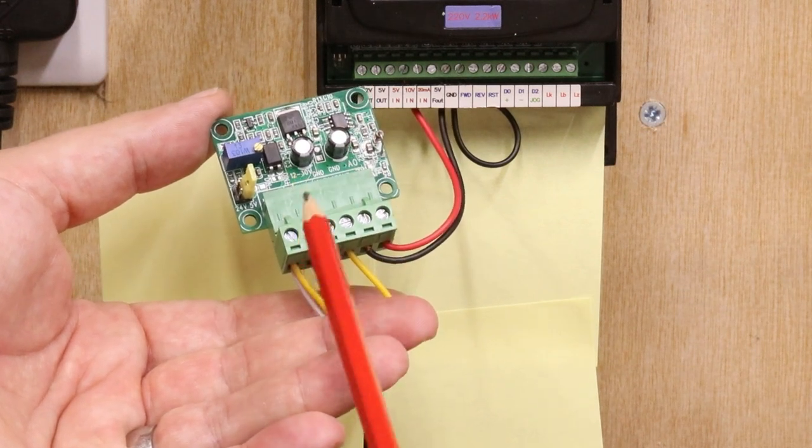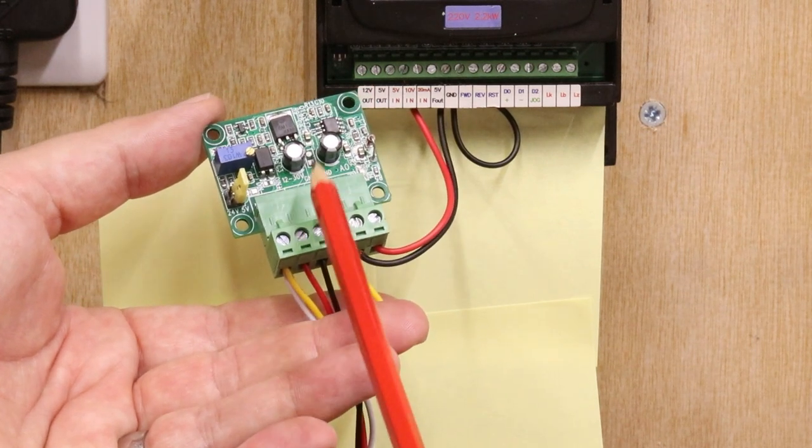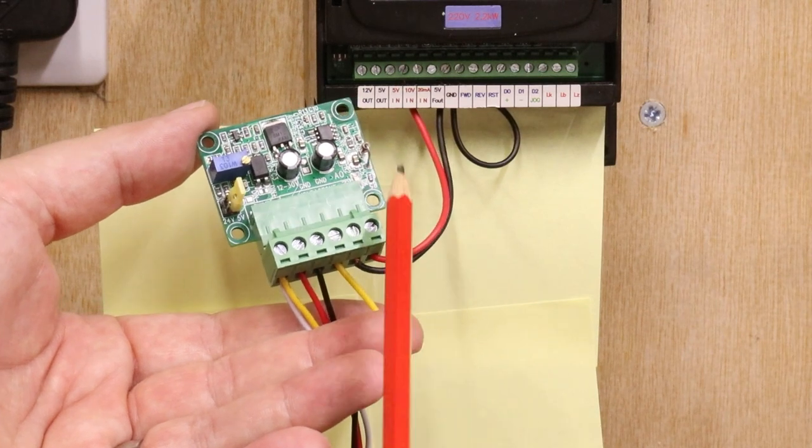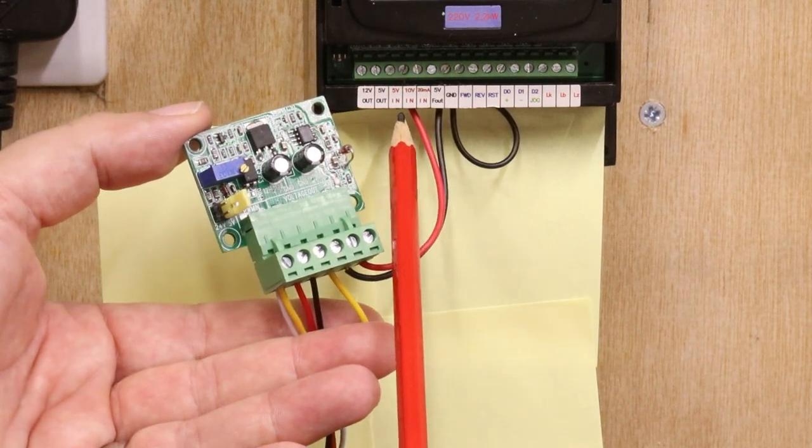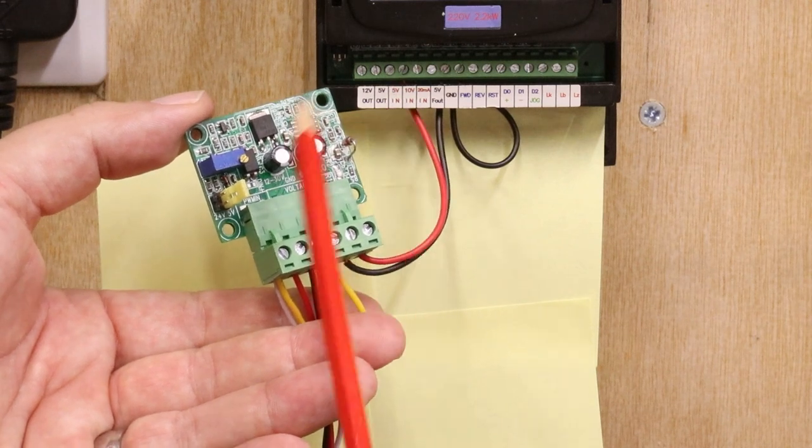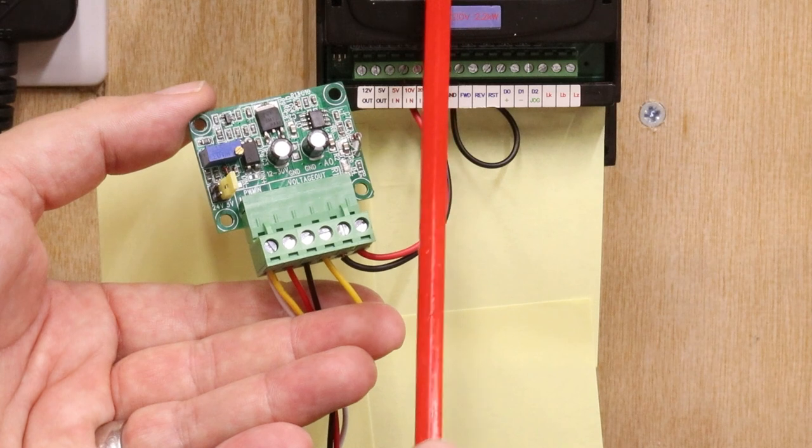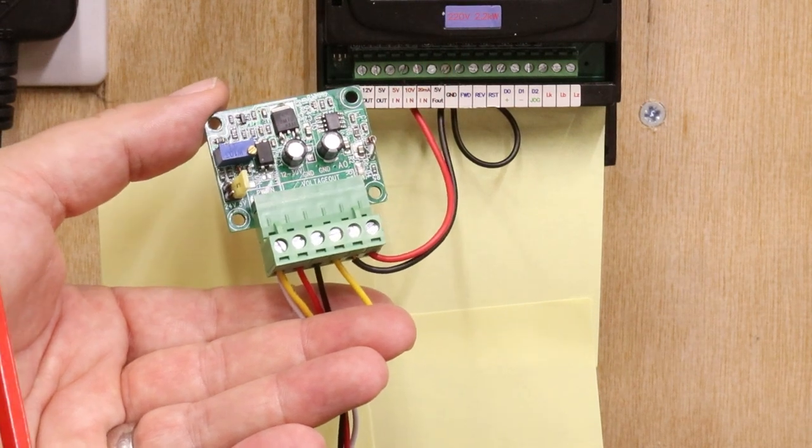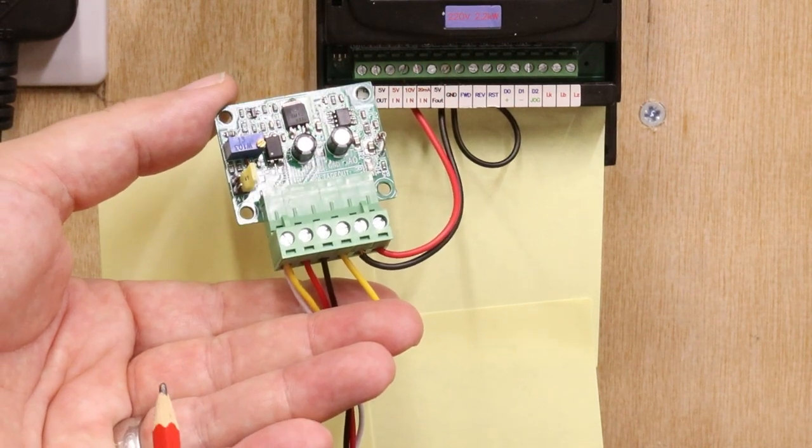Now the difference between this and the original setup is this will output up to 10 volts. So what we've had to do is move the input signal on the VFD from the 5 volt in to the 10 volt in, and obviously adjust that setting that I mentioned earlier on the setup itself in order to detect the 10 volt in.